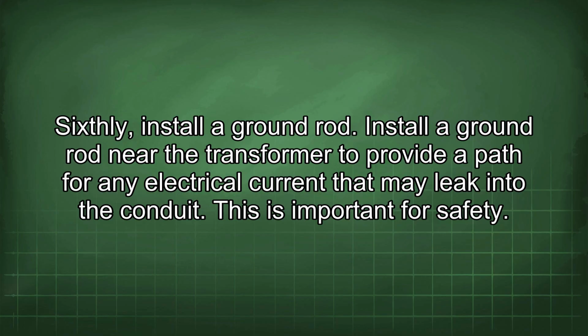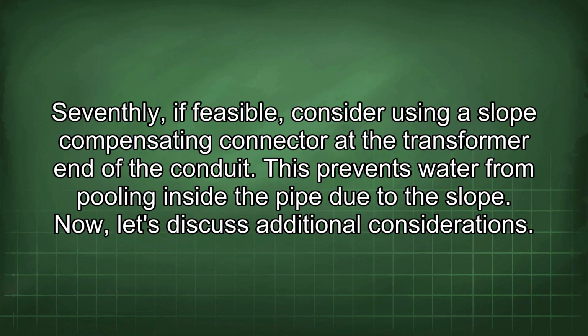Sixthly, install a ground rod. Install a ground rod near the transformer to provide a path for any electrical current that may leak into the conduit. This is important for safety. Seventhly, if feasible, consider using a slope compensating connector at the transformer end of the conduit. This prevents water from pooling inside the pipe due to the slope.